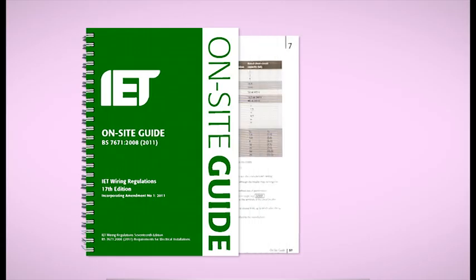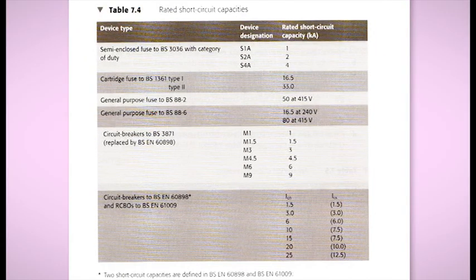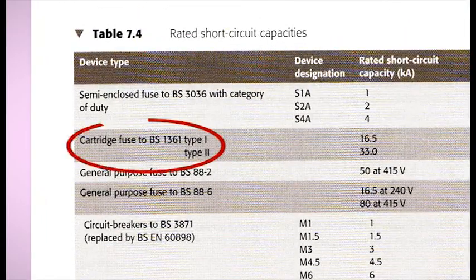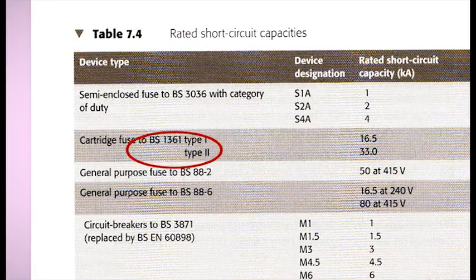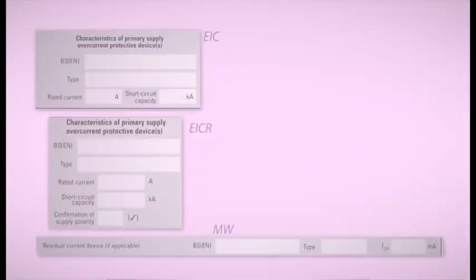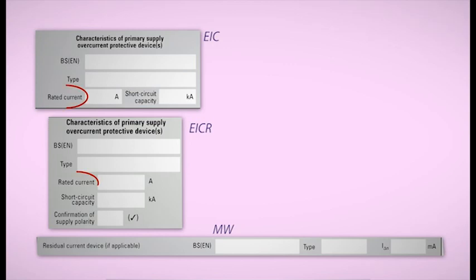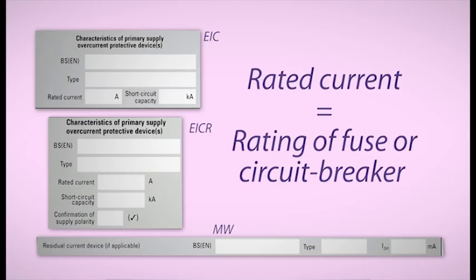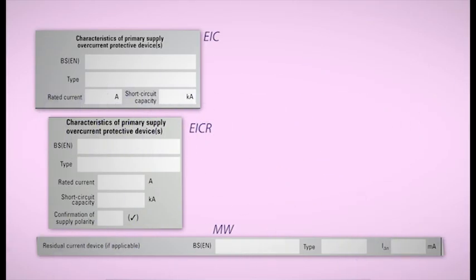There is data available to help you determine the type of device in the On-Site Guide. For example, a BS 1361 fuse used as a primary supply overcurrent protective device will be type 2. The next 2 boxes are rated current and short circuit capacity. The rated current is fairly straightforward, as it's the rating of the fuse or circuit breaker.